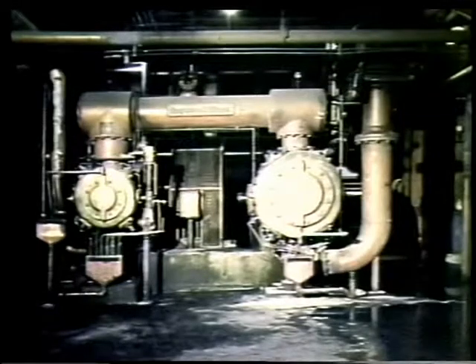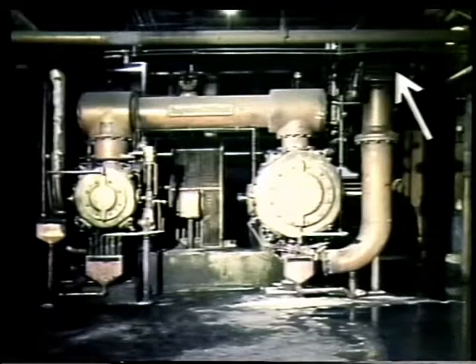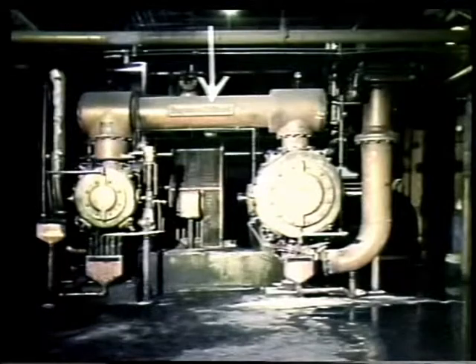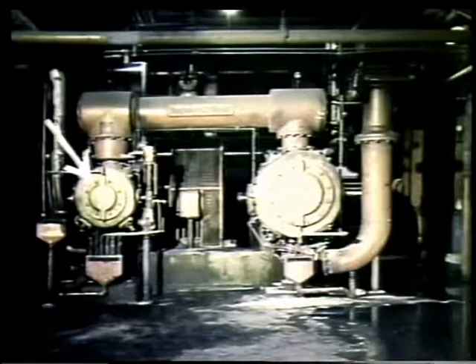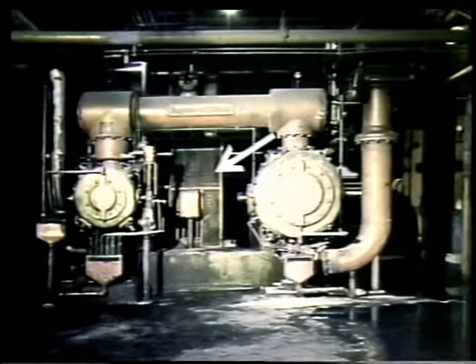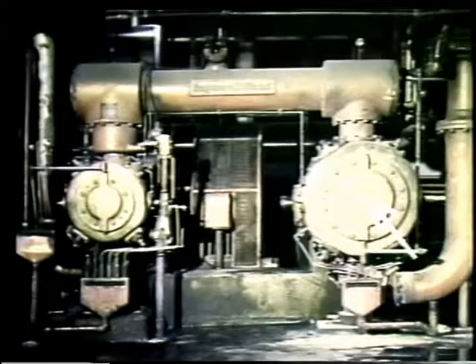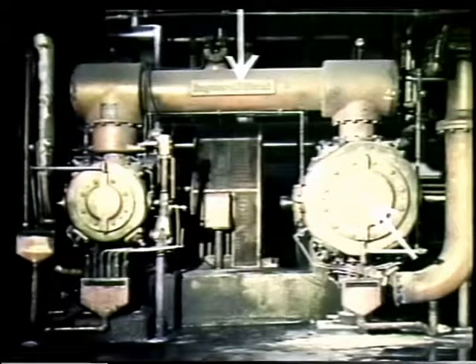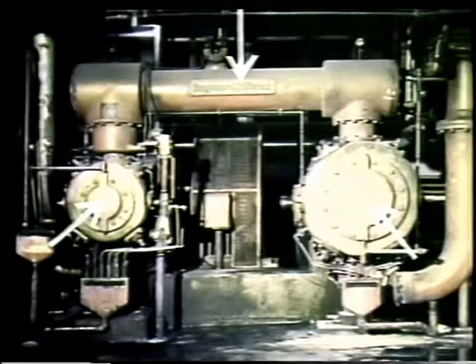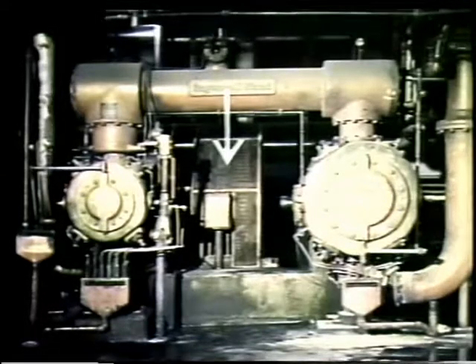Now, from this view, we can see the inlet filter, the first stage, the intercooler, the second stage, and the motor. The inlet filter keeps abrasive dust and other impurities from entering the compressor. The first stage compresses the air, and the intercooler cools the air before it enters the second stage to be compressed again. The purpose of the motor is to drive the pistons.